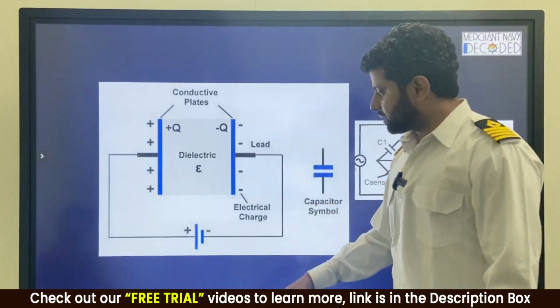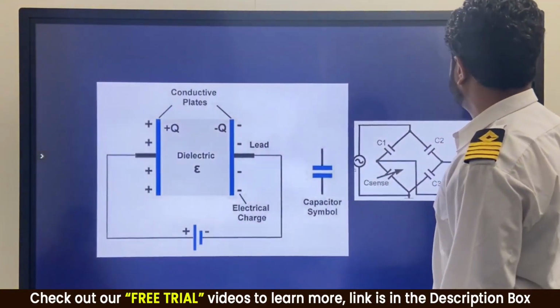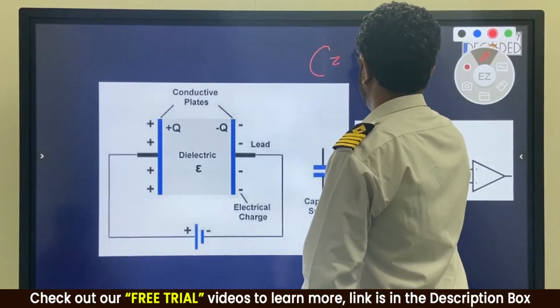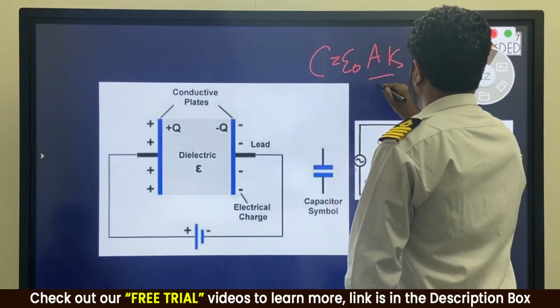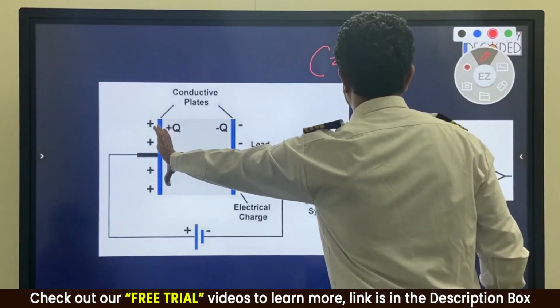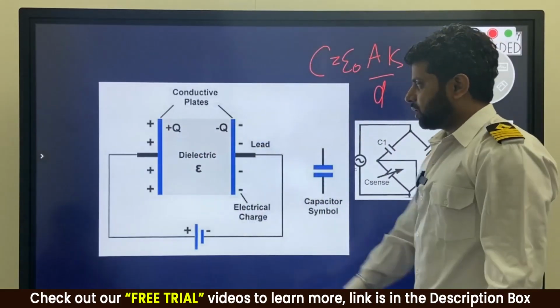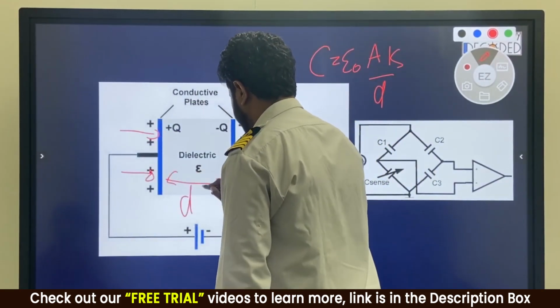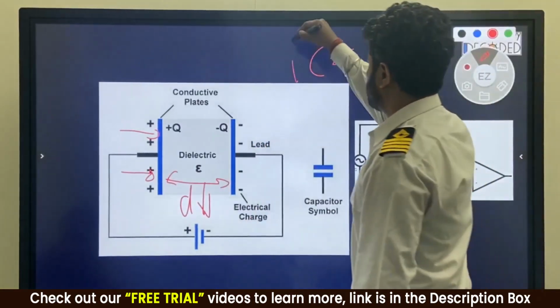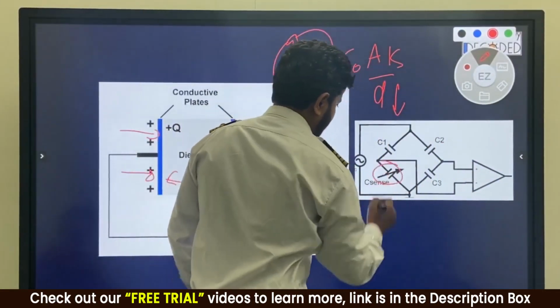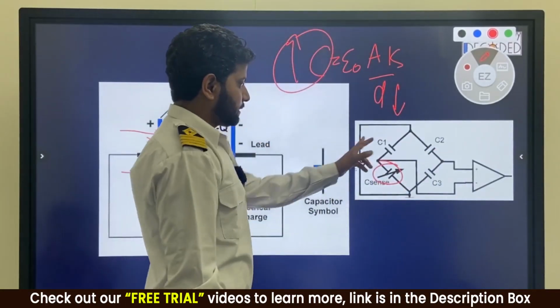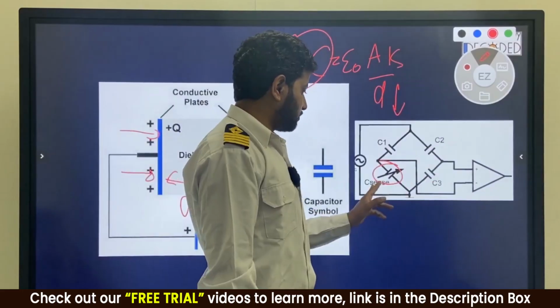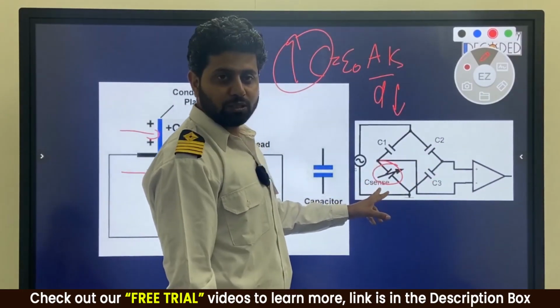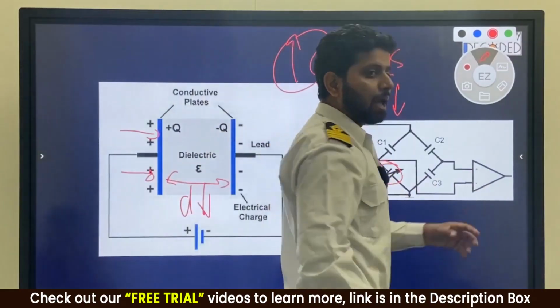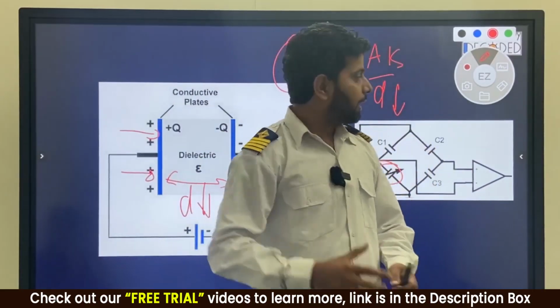Similarly over here, C is equal to epsilon naught A K by D. Again I am putting it over here, A K by D, where D is the distance between two plates, A is the area of the plate, and K is the dielectric constant in between. Now when the pressure is acting, say from over here, this is a fixed plate, this distance D is going to decrease. When this decreases, your C is going to increase. When your C changes over here, what will happen? This was a balanced Wheatstone bridge where C1 upon C2 is equal to C4 upon C3. This becomes unbalanced because these capacitances change. Then you measure this current, amplify it into a standardized instrumentation signal, and then you get an answer.